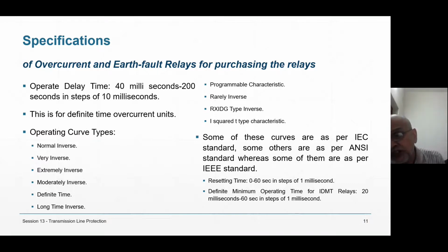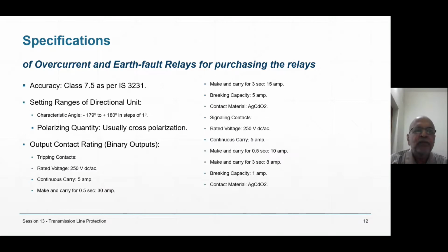Resetting time is 0 to 60 seconds in steps of 1 millisecond. Resetting is also in your power. Definite minimum time. You see, relays have definite minimum time. In older, traditional relays, it was only 2.3 seconds at TMS 1. You cannot set it. Here, you can set it from 20 milliseconds to 60 seconds, whatever you like. That minimum definite time is settable, right? Accuracy class 7.5 as per IS 3231.